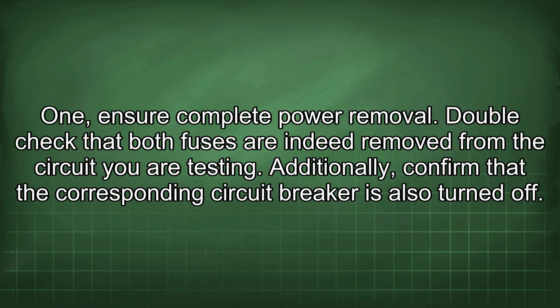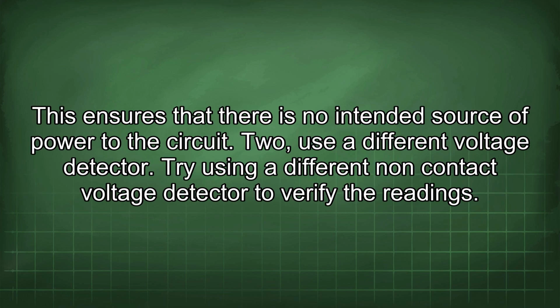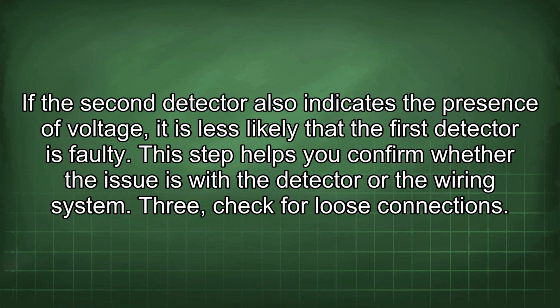1. Ensure complete power removal. Double-check that both fuses are indeed removed from the circuit you are testing. Additionally, confirm that the corresponding circuit breaker is also turned off. This ensures that there is no intended source of power to the circuit. 2. Use a different voltage detector. Try using a different non-contact voltage detector to verify the reading. If the second detector also indicates the presence of voltage, it is less likely that the first detector is faulty. This step helps you confirm whether the issue is with the detector or the wiring system.